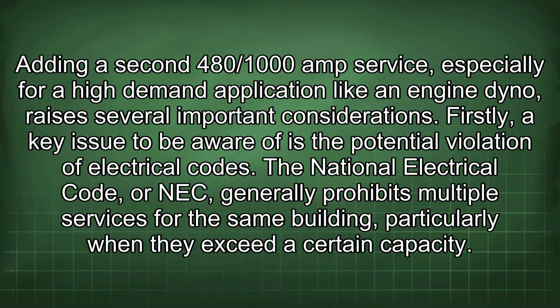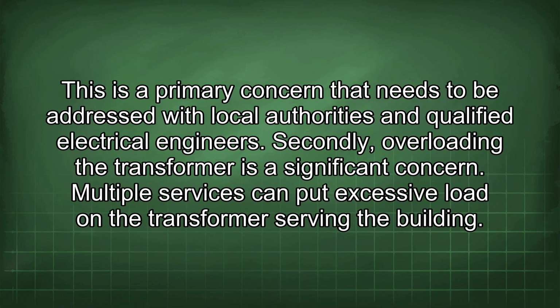Adding a second 480/1000 amp service, especially for a high-demand application like an engine dyno, raises several important considerations. Firstly, a key issue to be aware of is the potential violation of electrical codes. The National Electrical Code, or NEC, generally prohibits multiple services for the same building, particularly when they exceed a certain capacity. This is a primary concern that needs to be addressed with local authorities and qualified electrical engineers.